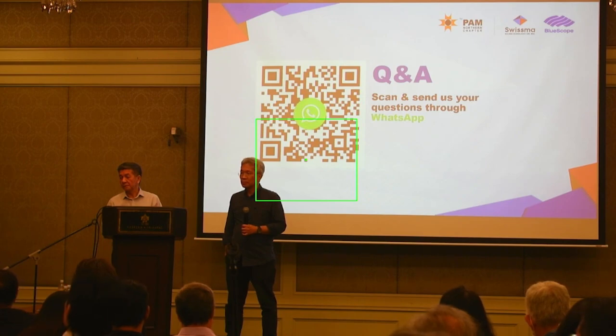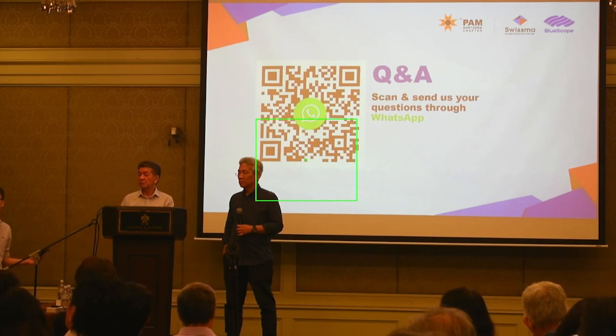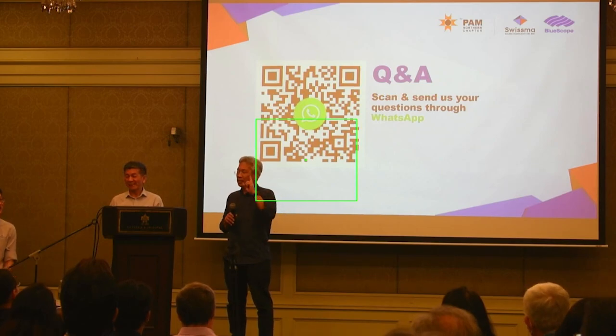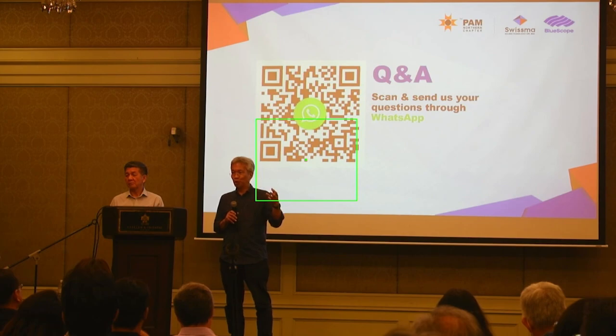Hi, I'm Architect Wei. Just a small question for either one of you. BS 8414 was recently put through. Architect Chong, you are currently under discussion with Bomba to finish the red book? Yes. So that means the guidelines are not comprehensively out yet, correct? Well, the law is out. And of course, the standard is the standard. The standard is not a standard for the material of the cladding, it's the standard of testing. It is not a prescription of what you can do on the wall. So 8414 is actually a testing standard.